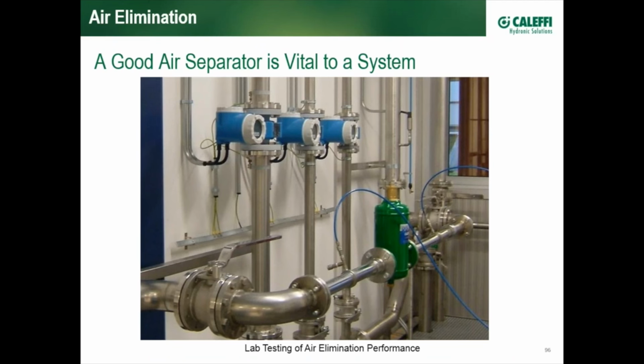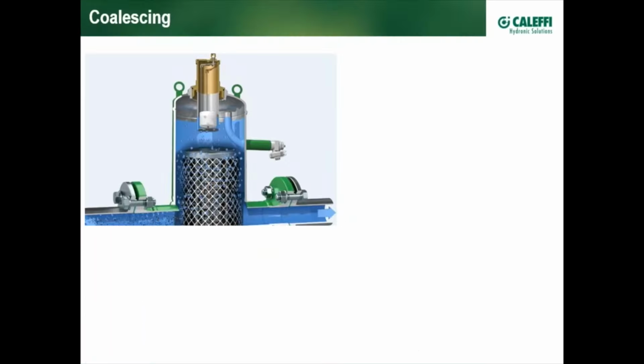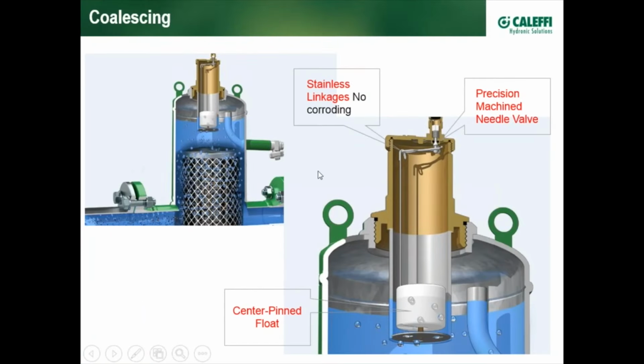And if truth be known, all coalescing air separators on the market, in terms of air elimination, are very efficient, way above 99% efficiency, whether it's Caleffi or Spirotherm or Taco, and we've done a lot of benchmarking. What's, I think, important to point out is some of the other details involved with construction. As we look at a coalescing type of air separator, in this case, Caleffi, we have a coalescing mesh where microbubbles that were created by either heating the water or incurring a pressure drop, lowering the solubility of air, bringing it out of solution. As those microbubbles collect and collide and become bigger bubbles, they eventually float to the surface, and the air cushion up here starts to increase.